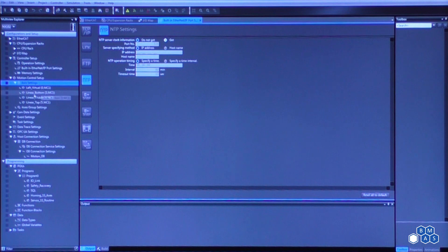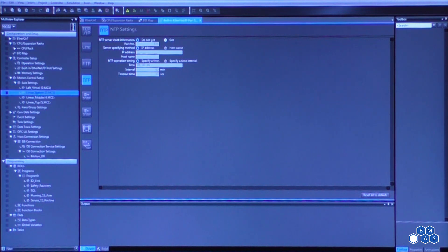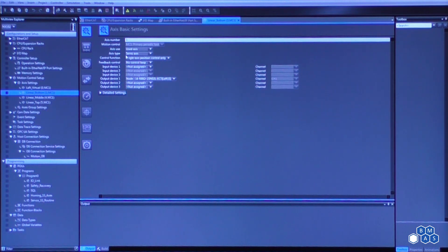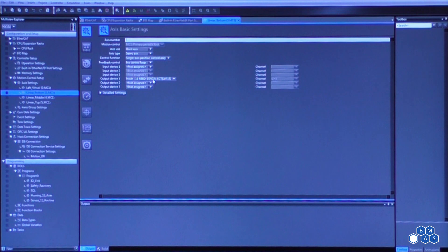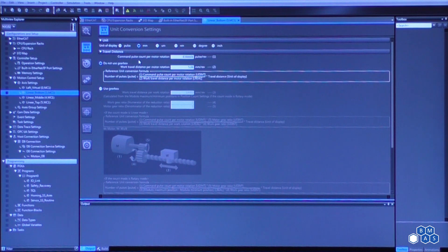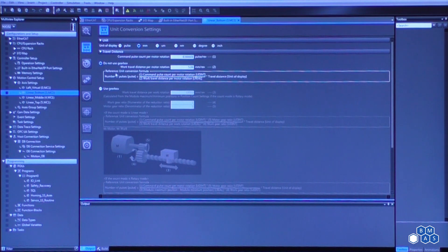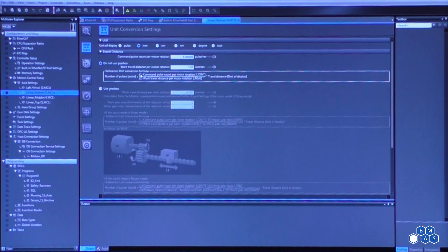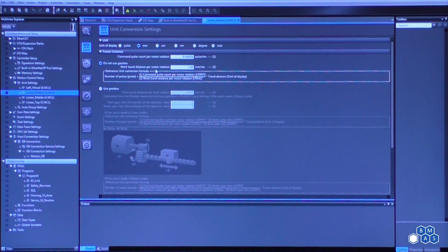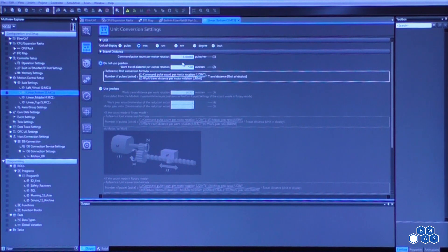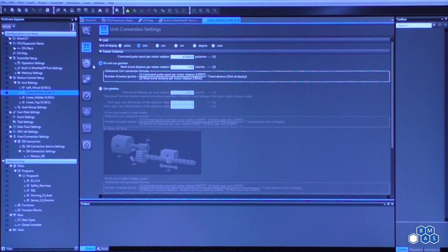So if we take a look at some of those that have been pre-configured, what we're doing is identifying the node that these were applied to and that it's going to be set up as a single axis position control. We have a servo axis, single axis position control axis, and the node that it was applied to. As we're going through this, it's going to ask, okay, so what is the command pulse count per motor rotation? So what this is asking is if we do not have a gearbox in our system, how far will we travel in one rotation of the motor shaft? So if the motor shaft rotates 360 degrees, what is the mechanical linear distance of travel that we will travel? In this case, it was 5.08 millimeters per rev, and we will have 8,388,608 pulses per revolution of that shaft.